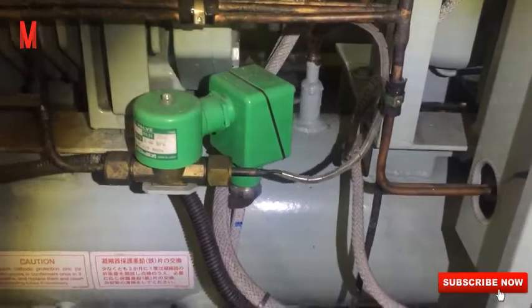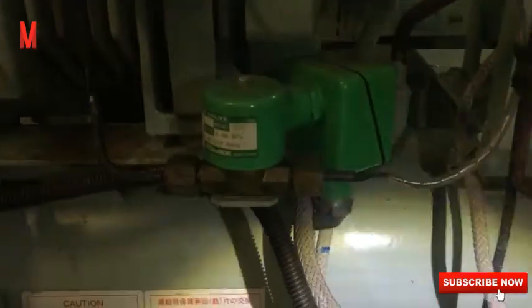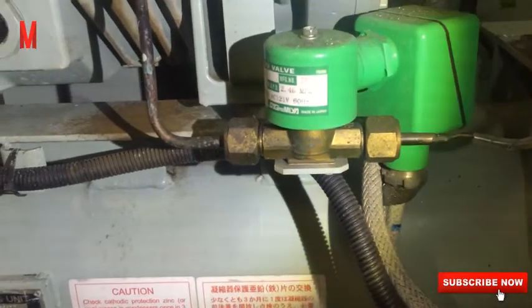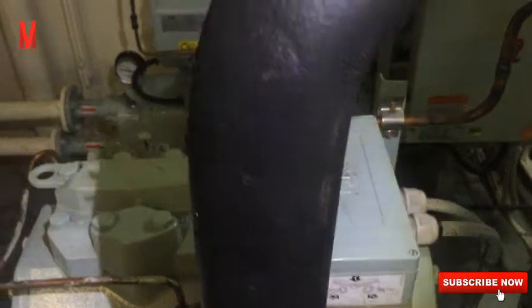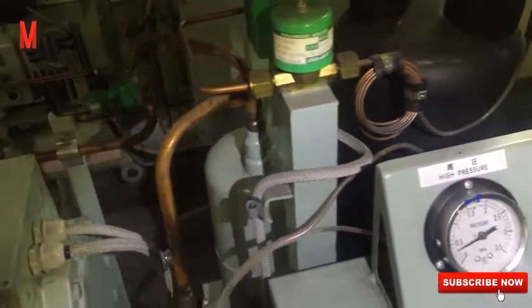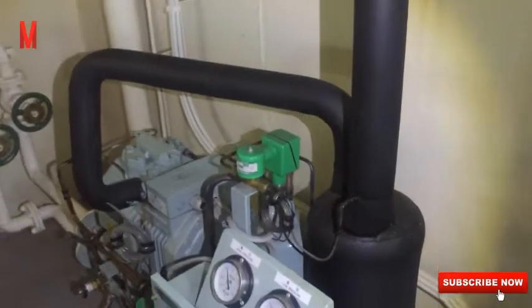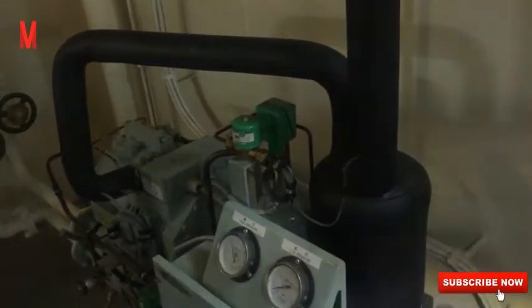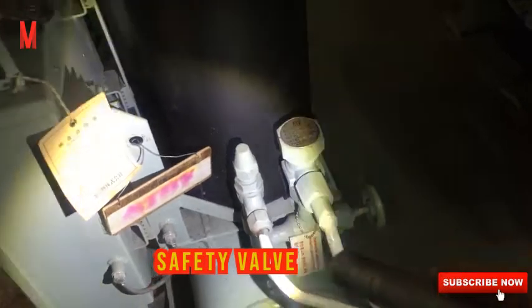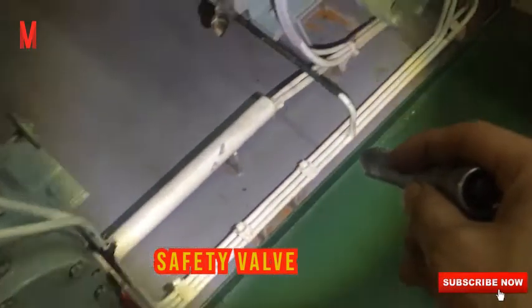And then we have the accumulator. This accumulator prevents the wet compression or excessive liquid backflow. So dito pinoprotektahan yung compressor from wet compression. So dapat puro dry compression lang or puro gas refrigerant yung magsasuction dun sa compressor, kasi nasisira yung compressor kapag nag-compress siya ng liquid. And then we have the control box. This control box is used to contain the protective devices, and this runs the control devices.